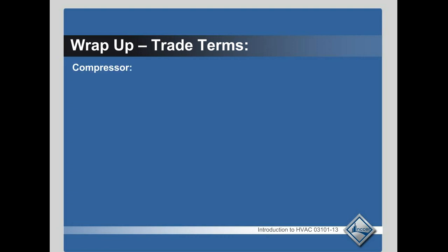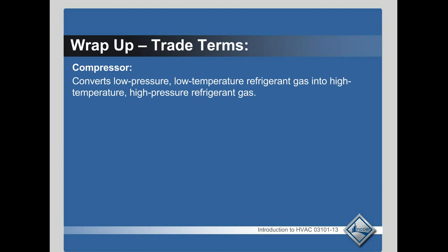So the compressor — that is the part of the refrigeration system that converts that low pressure, low temperature vapor into high temperature, high pressure refrigerant gas. It is pretty much the heart of the refrigeration cycle that pumps the refrigerant around. It is also the dividing point between the low pressure system and the high pressure system — one of the dividing points.